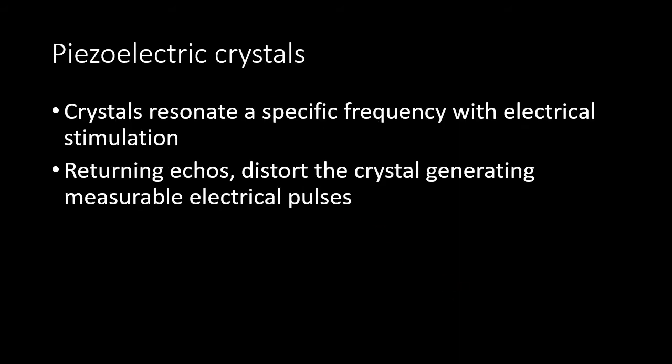Traditionally, we use piezoelectric crystals to generate the ultrasound pulse. Within each probe there are these specialized crystals. When you apply a certain electrical current to the crystal, it will resonate at a specific frequency, creating mechanical energy transmitted as an ultrasound wave into the tissue. When that ultrasound wave reflects off of the tissue and comes back to the probe, the mechanical energy distorts the piezoelectric crystal and generates an electric impulse. These crystals are unique in that they can both resonate when stimulated with electricity and generate electricity when distorted by mechanical energy.